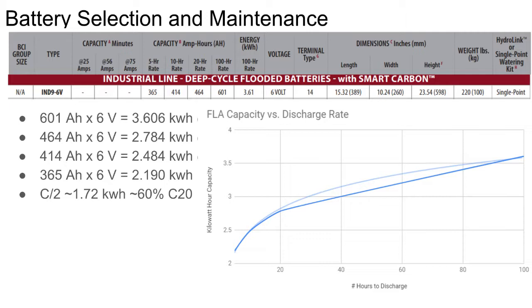And you could even go a step further and say, well, actually, I'm going to go back to that tankless water heater, but I'm only going to use it at times when my solar array is on full blast and my batteries are fully charged. And so what would be stranded electricity, I'm going to use a tankless water heater to just shave it off the top. And at that point, I'm not using my battery to run my tankless water heater. So you could develop a control system where a high load device is actually very useful and not the enemy in these homes.